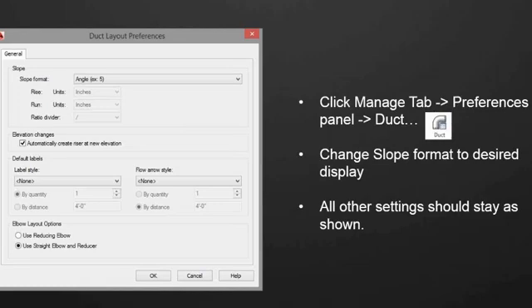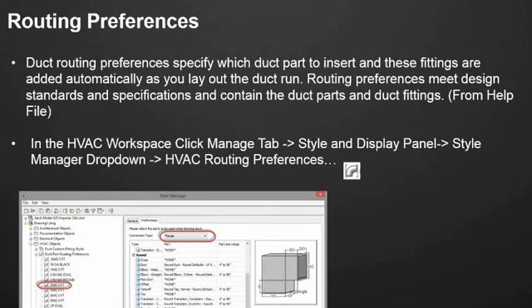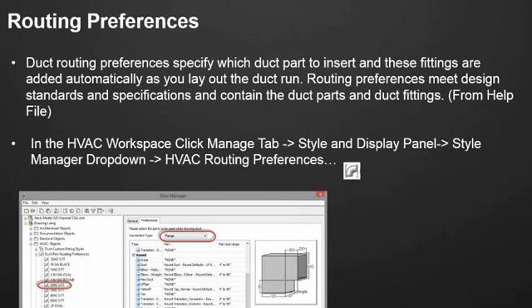Our template should be set up with these settings already, but I believe it is a per-template setting. One of the most important things in routing duct to make sure that you have correct are your routing preferences. Your routing preferences specify which duct to insert, and these fittings are added automatically as you lay out the duct run. Routing preferences can be used to meet your design standards and your specifications and contain all of your duct parts and duct fittings. That's almost verbatim from the help file. If you just open up the help file and type in duct routing preferences, you'll get to this text and you can read a lot more about them.